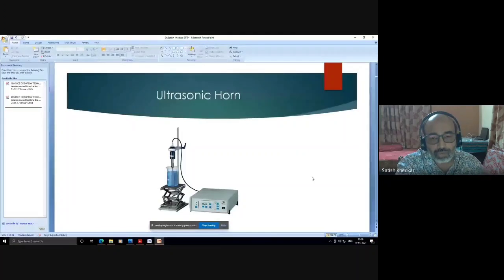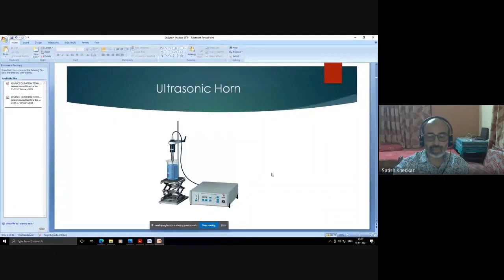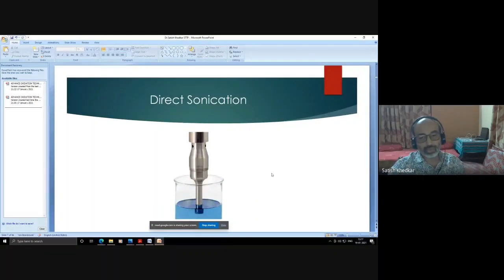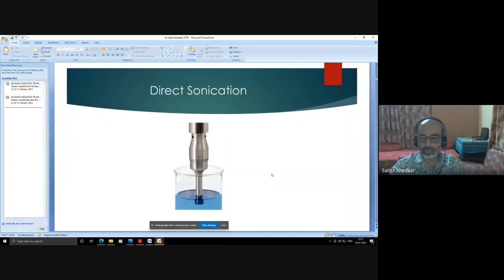And this is the ultrasonic horn, which is used for sonication of small quantities of liquid or test samples. If you mount this ultrasonic horn inline in a pipeline, then continuous sonication is also possible. For continuous sonication, you have to fit this ultrasonic horn into the pipeline so that continuous sonication of the pipeline liquid can take place. So sonication is not only a batch process. It can be practiced on a continuous basis also, provided the arrangement is made for that purpose.